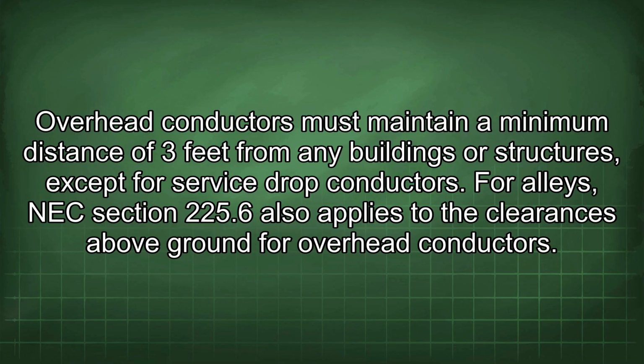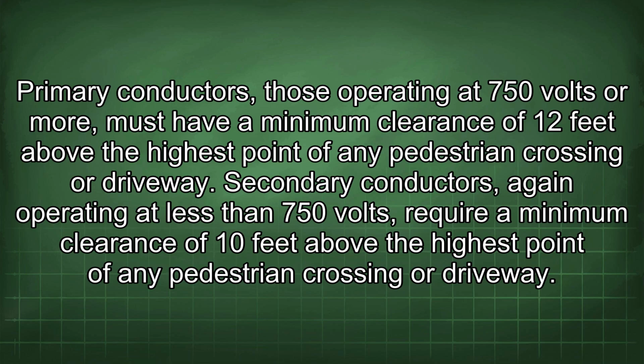For alleys, NEC Section 225.6 also applies to the clearances above ground for overhead conductors. Primary conductors, those operating at 750 volts or more, must have a minimum clearance of 12 feet above the highest point of any pedestrian crossing or driveway. Secondary conductors, again operating at less than 750 volts, require a minimum clearance of 10 feet above the highest point of any pedestrian crossing or driveway.